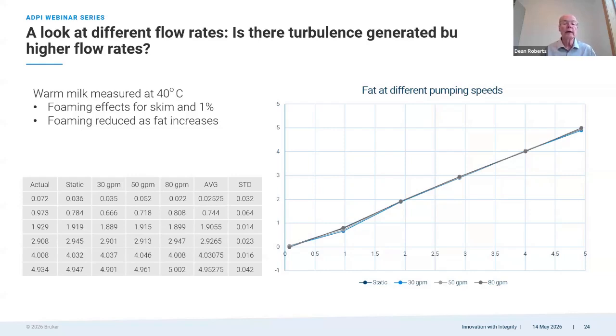But when we get up into the 2% through the 5% levels, we're really close to the reference value at the different flow rates, and it looked really good. Our conclusion here is that it's not the flow cell causing the changes in those values, because if it were turbulent flow being developed by the flow cell, we would have seen that in both the 40C and the 5C. So we're thinking that the slope and offset really is due to the temperature. Next slide, Andy.